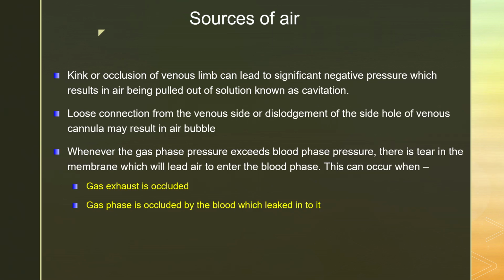First is from the pre-pump lines. The pre-pump line is a negative pressure line. So any disconnection or any crack in the pre-pump line will give rise to air getting sucked into the oxygenator or the circuit. That is one source. Second source is when there is too much negative pressure. If your pre-pump pressure becomes more than -200, it causes cavitation and air is generated inside the circuit by itself. So that can be another source of air in the circuit.